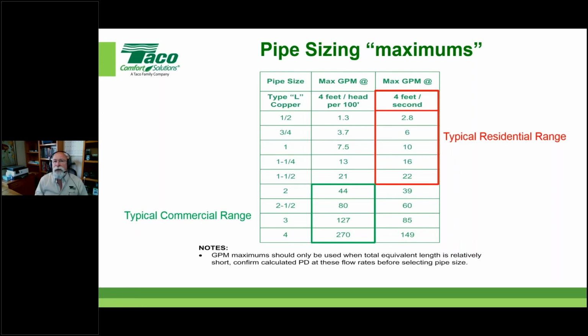What we see in primary secondary quite a bit is that we're using a bigger delta T across the boiler side so we can get by with smaller pipe sizes. For instance, we might have 1-inch headers coming off a condensing boiler that go into a 1.5-inch secondary system pipe. Hopefully that answers the question.